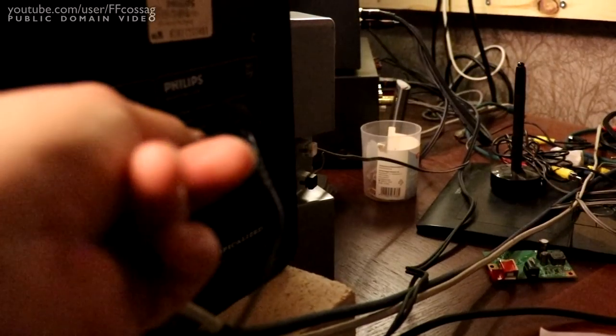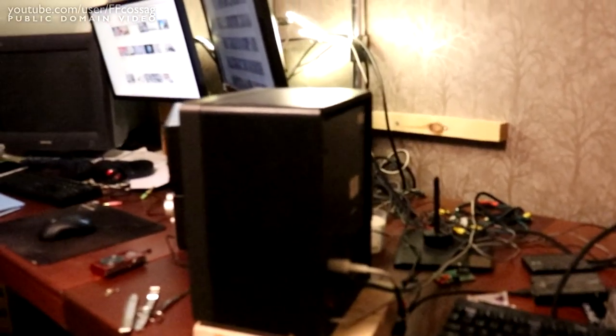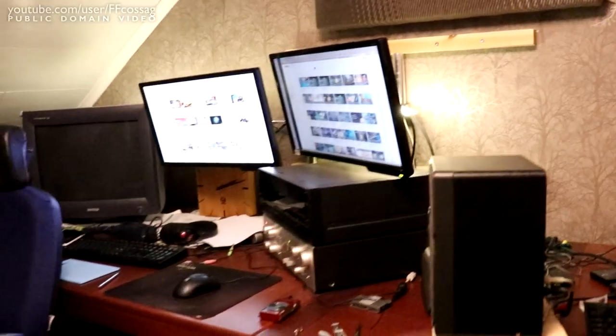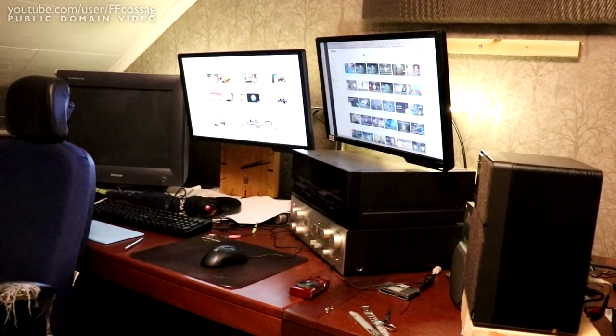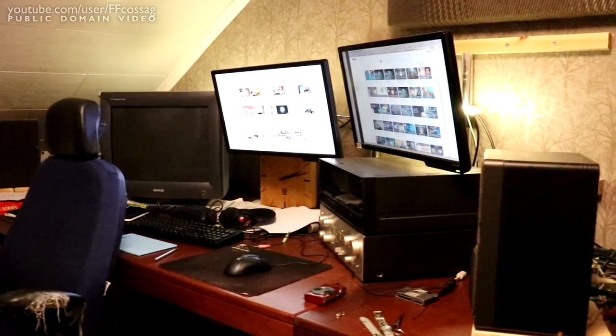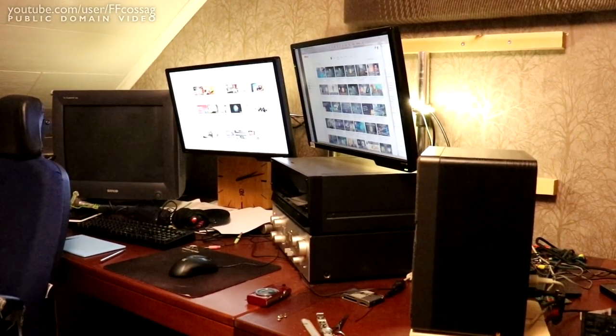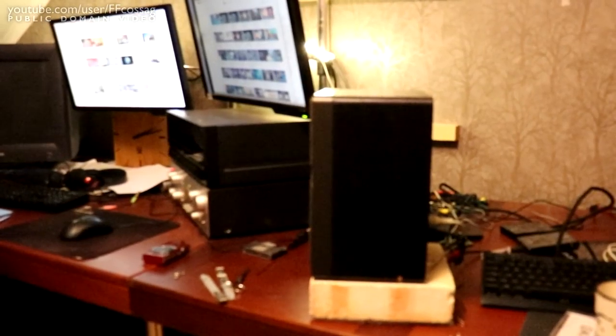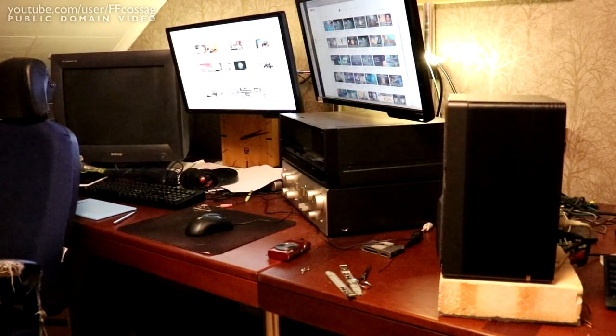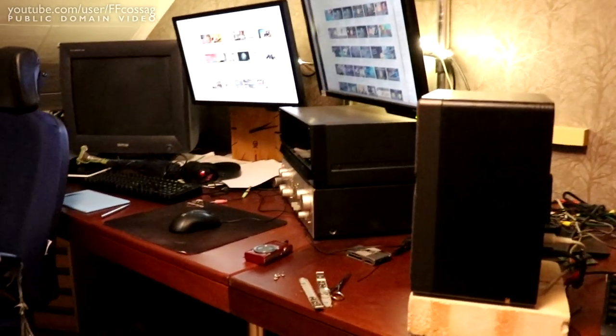It seems that the Socomec UPS, despite being an online UPS, does not have good enough line regulation to actually deal with a varying load of a PC without getting ever so slightly varying AC voltage. Because I think that's what we're hearing. The voltage is kind of sagging just a bit with the varying load of the computer, and that's making the transformer work harder and lighter in order to keep the voltage charged in the capacitors of the audio gear, making the transformers hum from mere load transients rather than the distortion we're seeing with the industry next door.